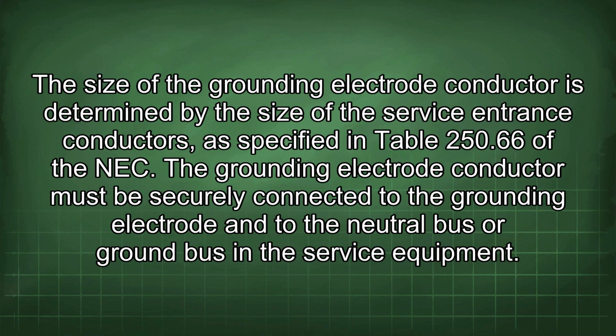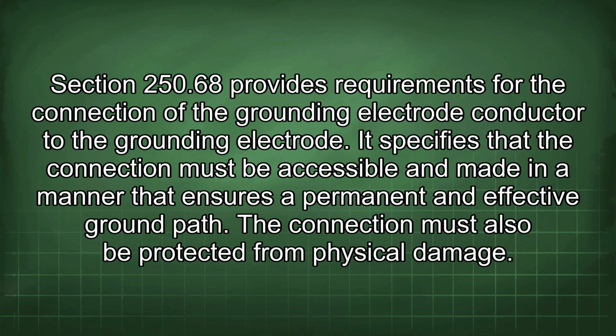The grounding electrode conductor must be securely connected to the grounding electrode and to the neutral bus or ground bus in the service equipment. Section 250.68 provides requirements for the connection of the grounding electrode conductor to the grounding electrode. It specifies that the connection must be accessible and made in a manner that ensures a permanent and effective ground path. The connection must also be protected from physical damage.